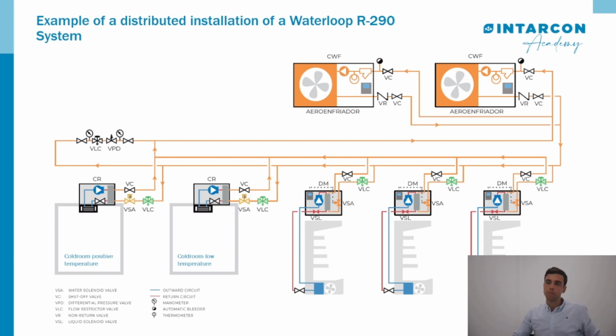Also, a recommendation will be the use of automatic bleeders at the highest point of the installation to eliminate trapped air, or you could even incorporate air traps and drain valves at the lowest point.